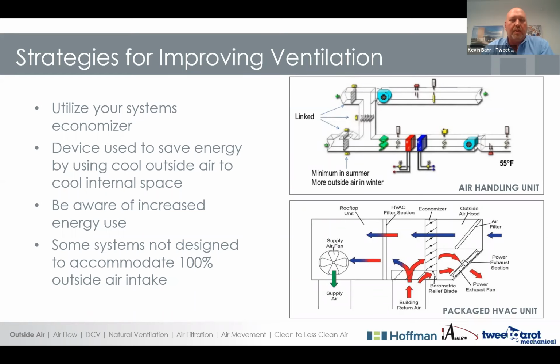Also note, if you do manipulate those settings, record where they were originally set so you can go back to that once we reach a point of normalcy. Most air handling units and package units have the capability to adjust the outside air. The amount of outside air into a facility is dictated by code requirements, and sometimes by specific requirements of your process or facility. As you change these, you're overriding the minimum amount set for your design.